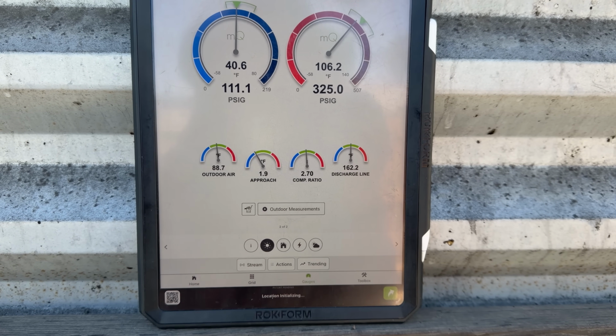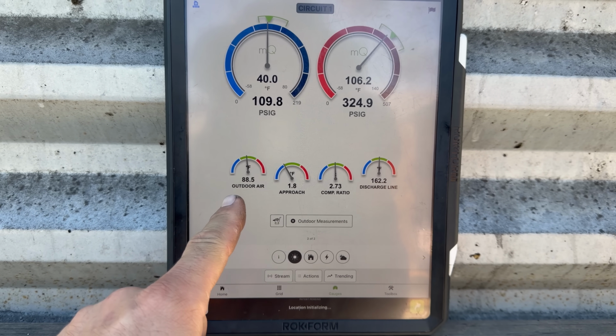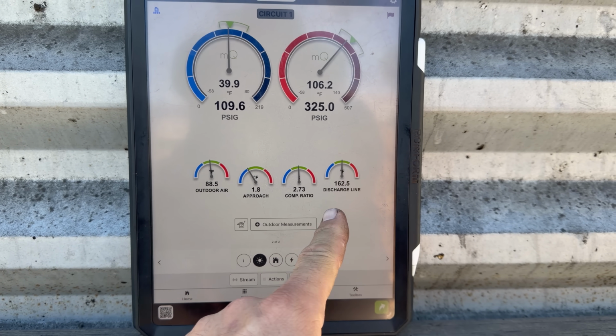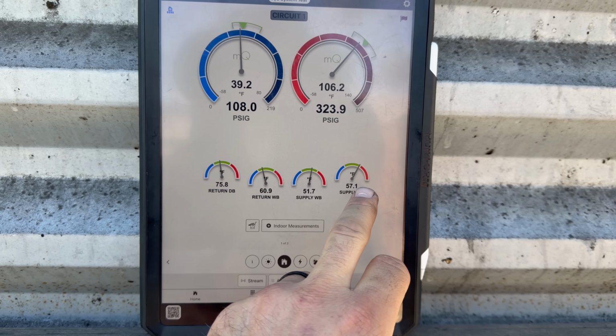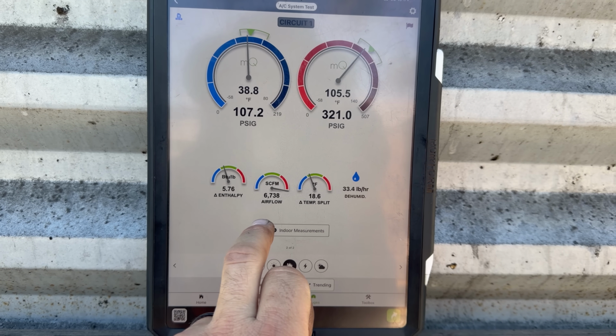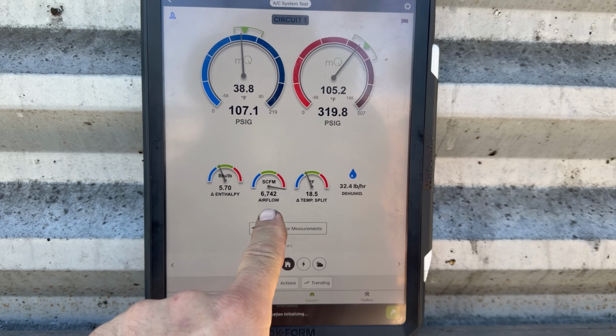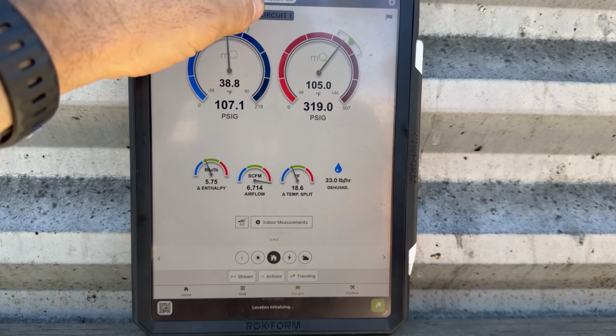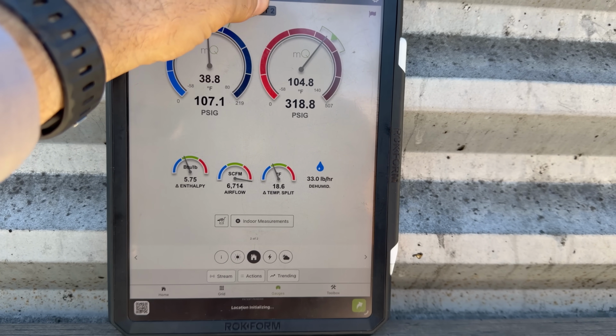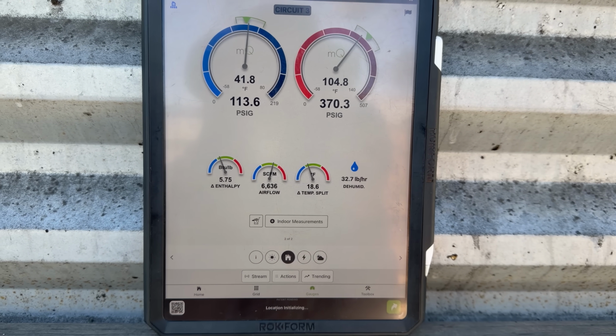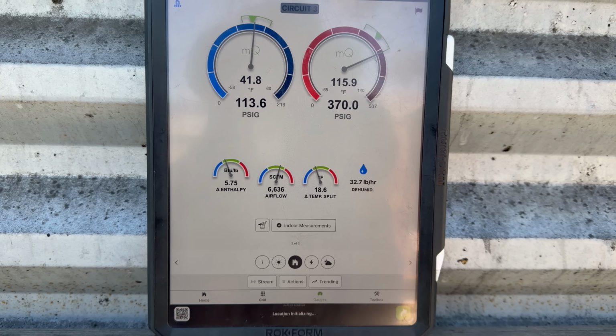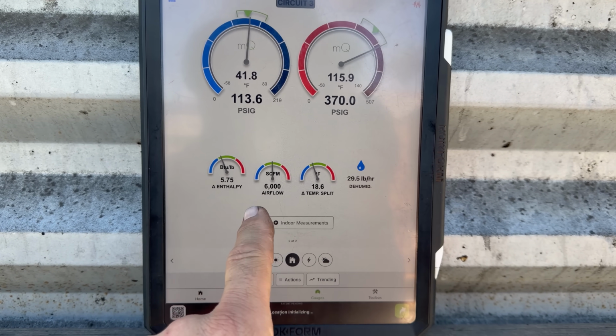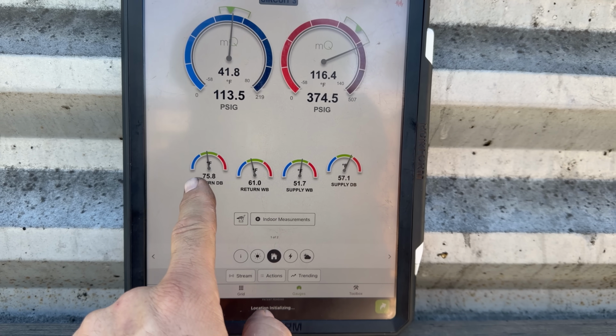Vitals look fine. We can scroll over. Outdoor air temperature is almost 90 degrees. Discharge line seems good. Don't see any issues there. Okay, temp split does not seem horrendous. The airflow, that's a skewed number. Hang on. In order to see the true airflow, you've got to go to the third stage. And then you see how it shows that it's good because it's looking at all three compressors now. Okay, so airflow seems fine.